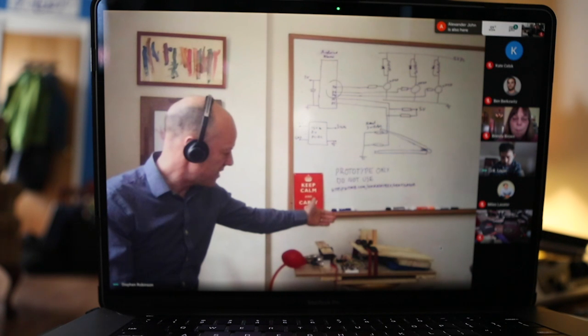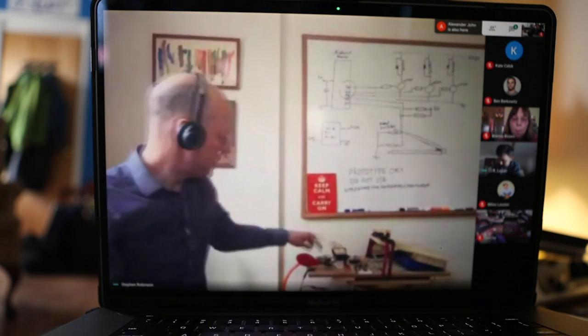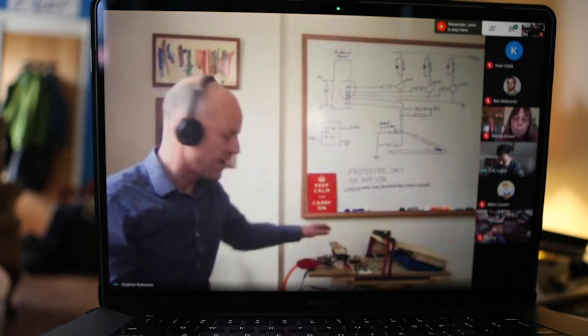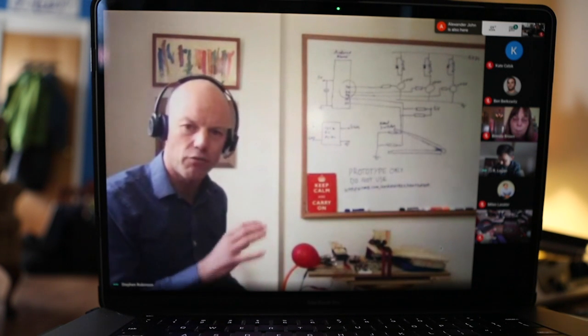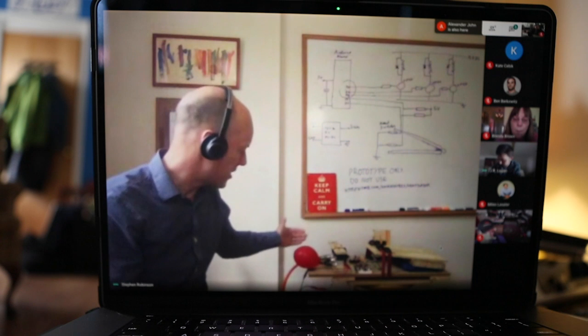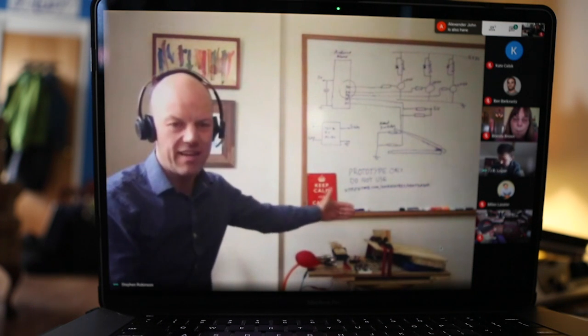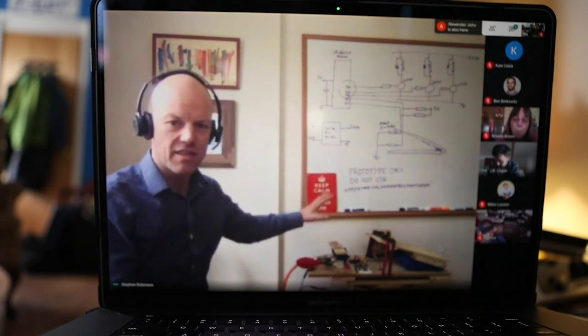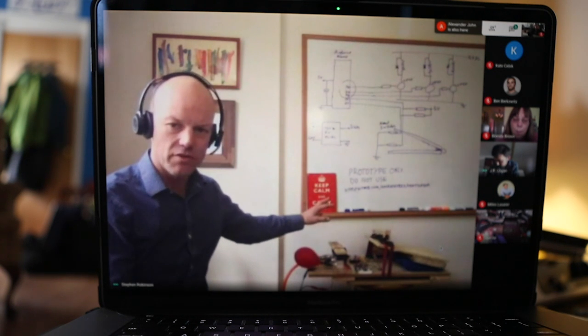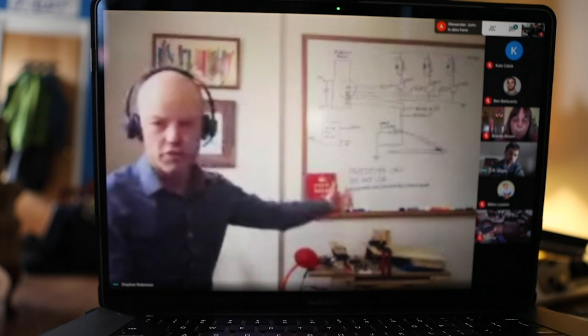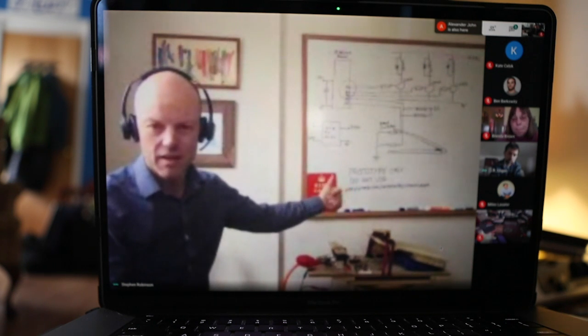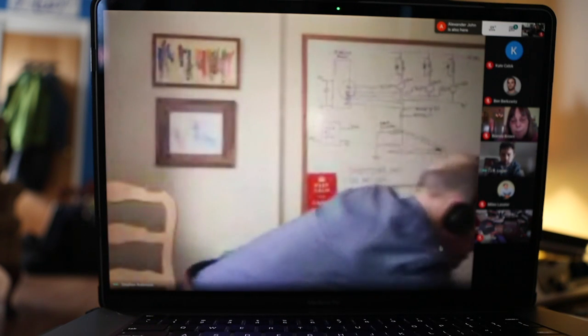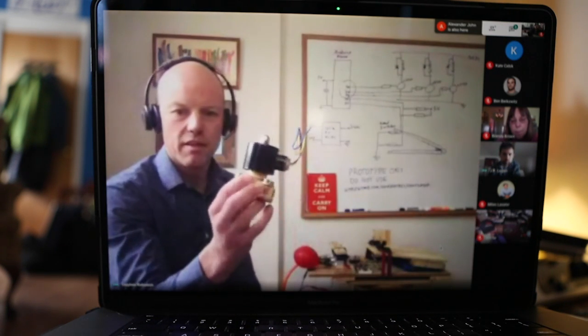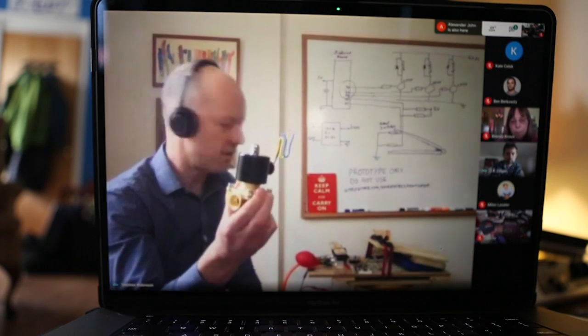Points to make: these particular valves are quarter-inch valves and allow a certain amount of throughput of pressure. On the intake side, that's actually a reasonable size of valve. The question might be more on the exhausting side of the ventilator - you may want a greater flow rate. So for something like that, things to experiment with would be larger bore capable solenoids.